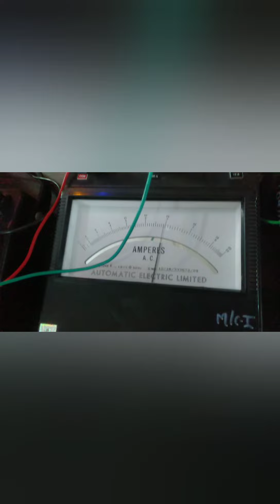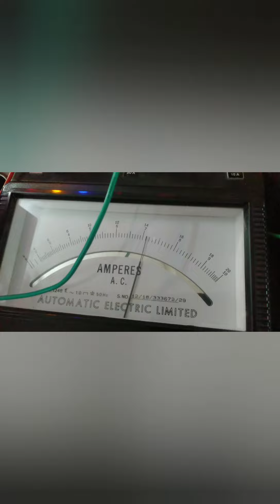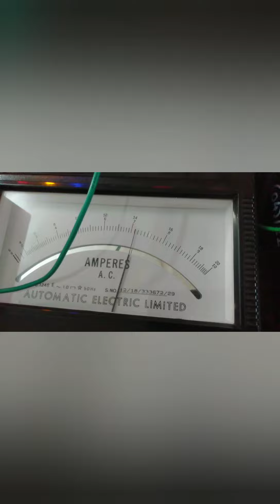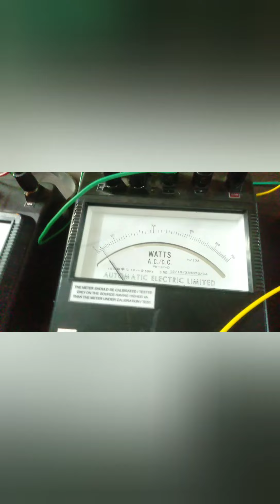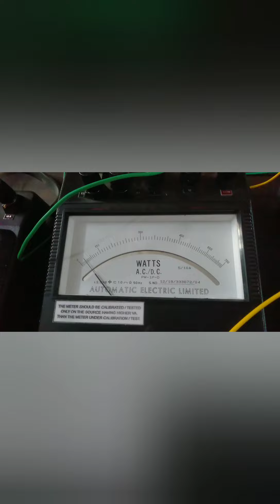Using this dimmerstat, we are increasing the value of current till 7.1 ampere, because this 7.1 is nothing but the rated current. For that 7.1 current, you can see the voltage is 80 volt at the time of 7.1 current. W1 is 60, again the multiplying factor is 8, so 60 into 8. Then W2 is 10, I think.